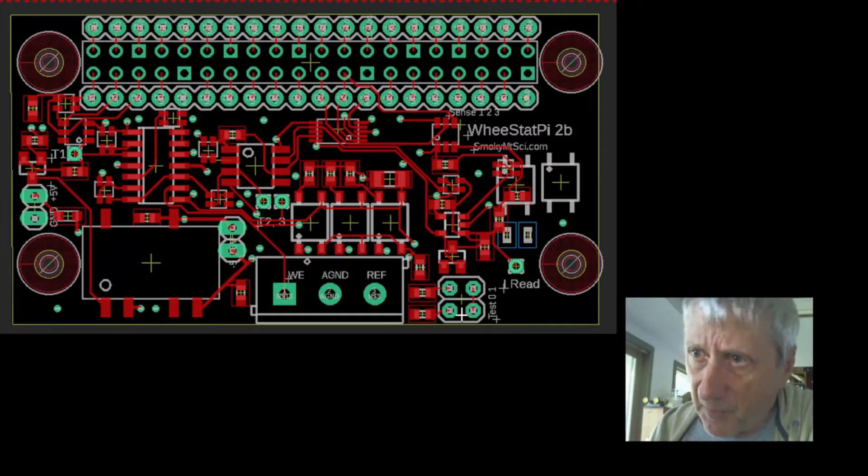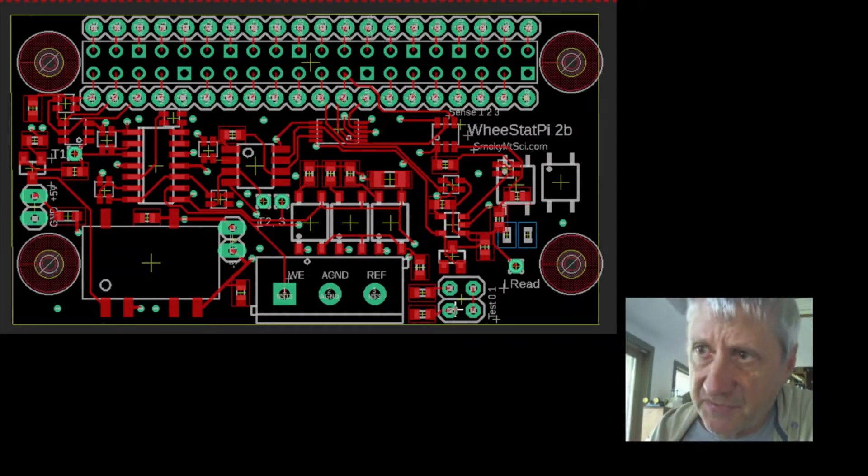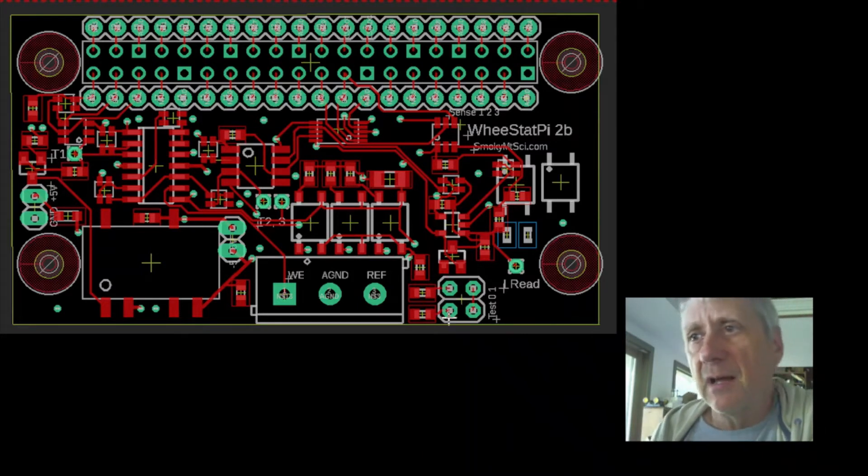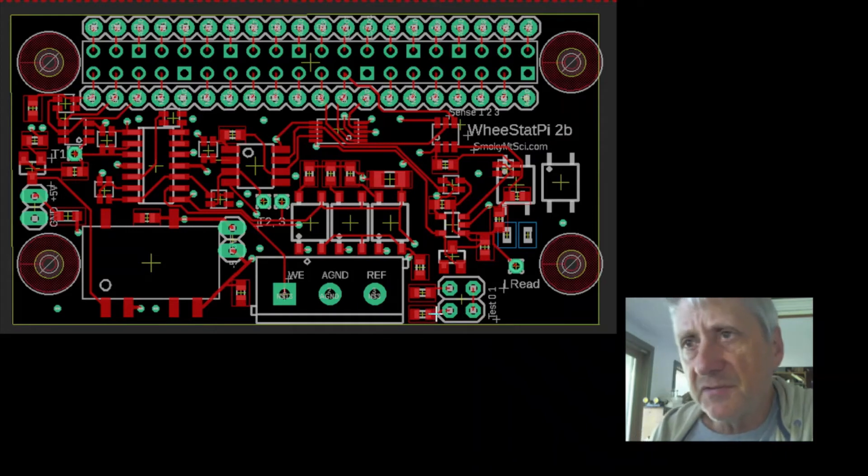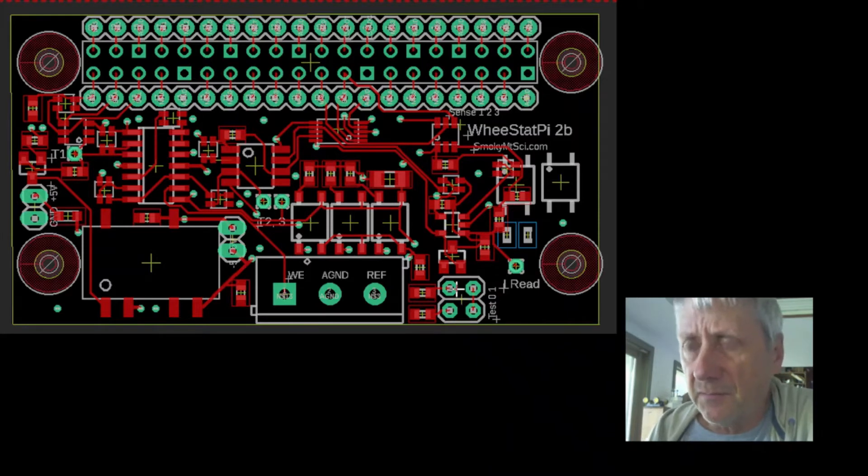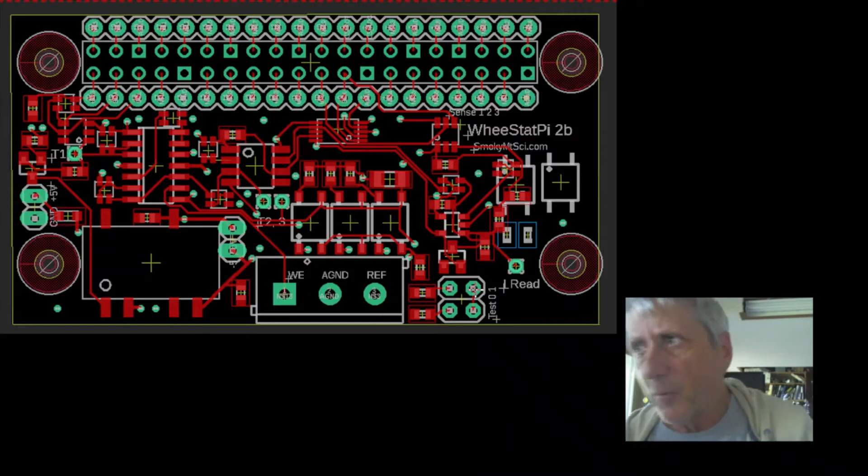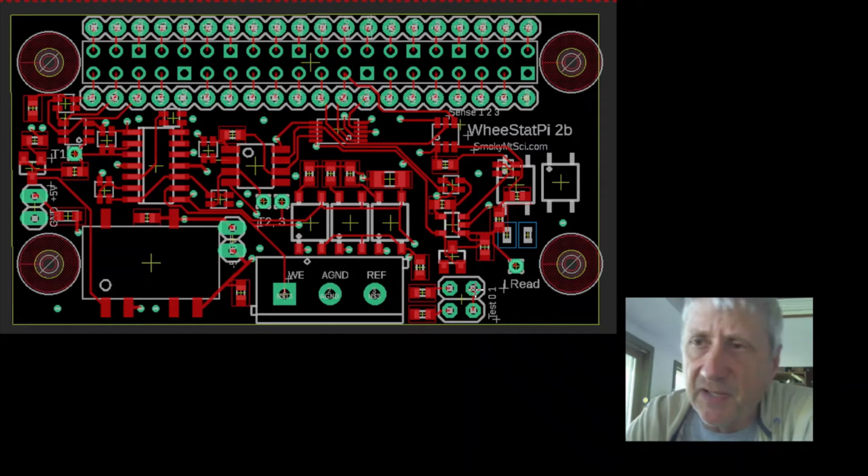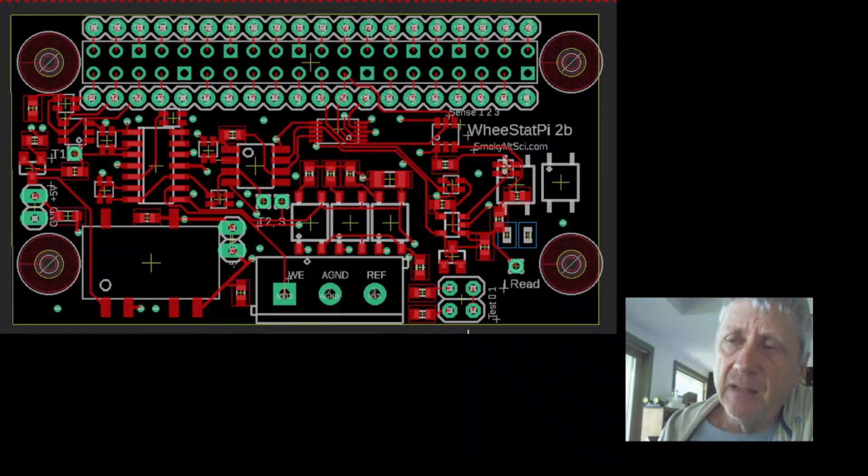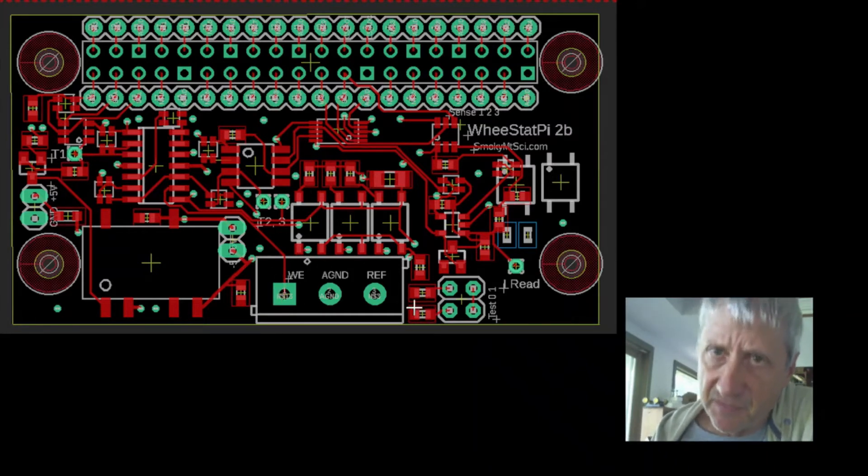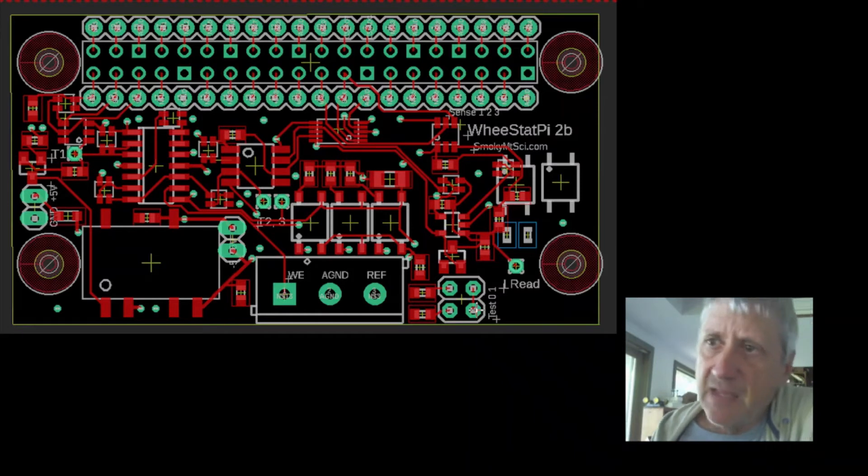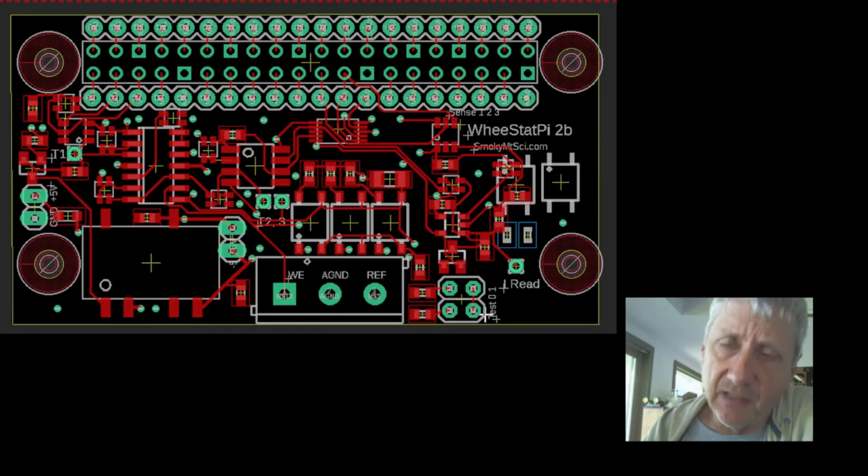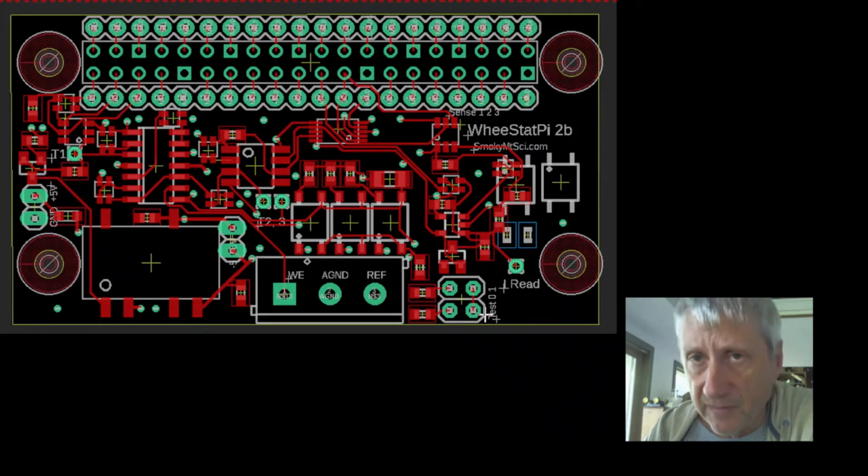There's a jumper here that will connect test resistor 0. There's a jumper up here that will connect test resistor 1. I believe test resistor 0 is like 267 kiloohms. Test resistor 1 is 5.1 megaohms. And what happens when we have these connected is that we are connecting ground to the working electrode through those test resistors.